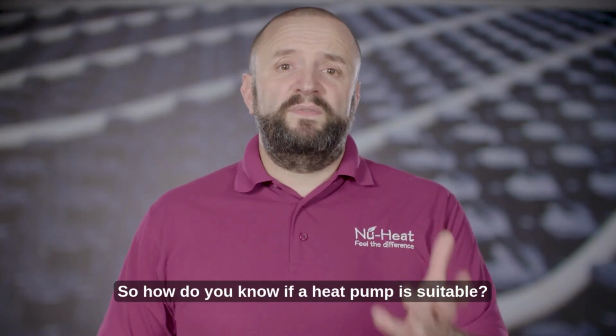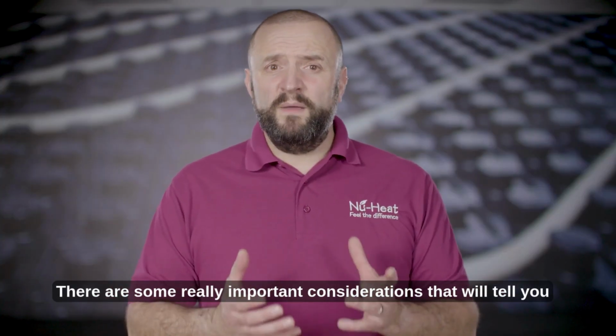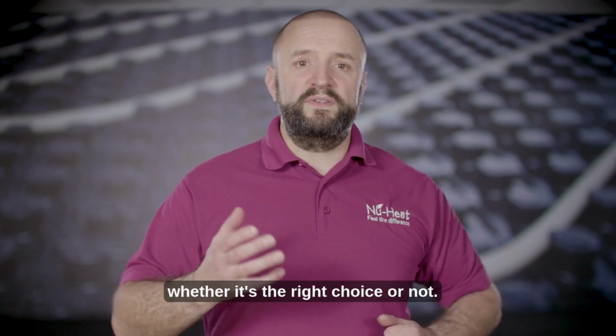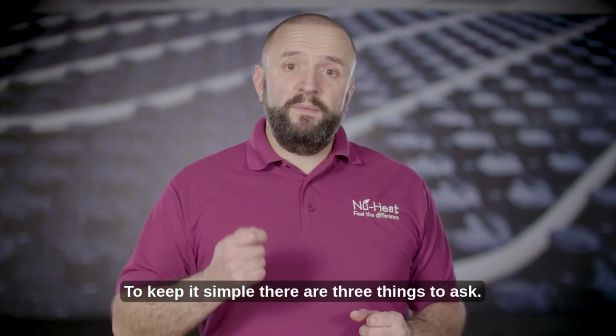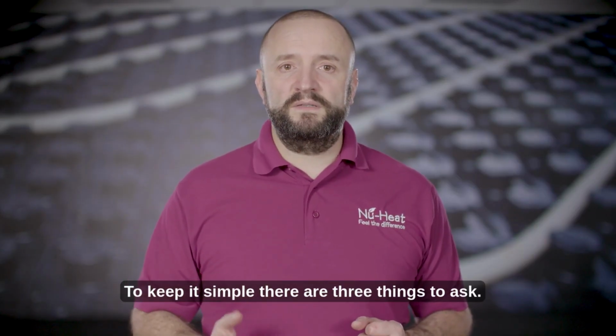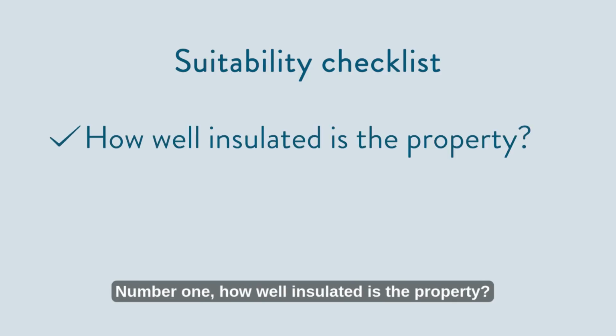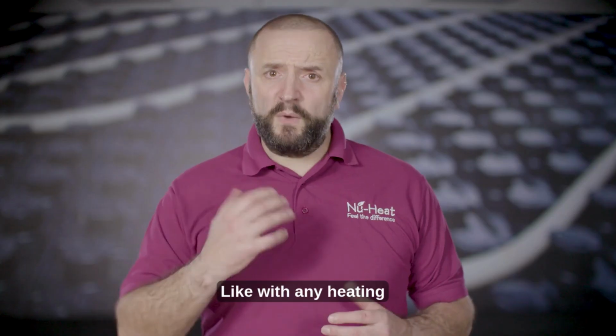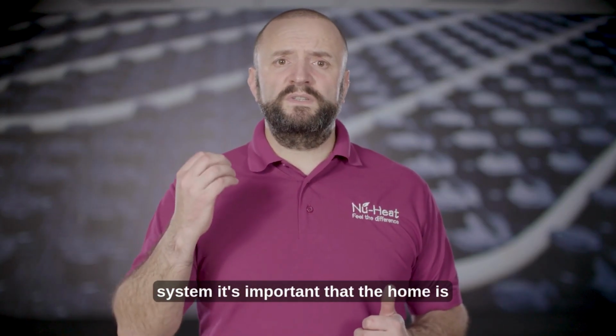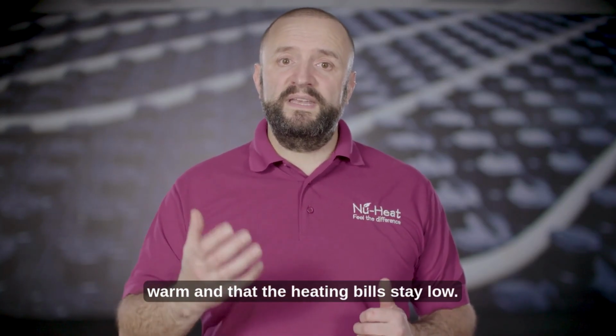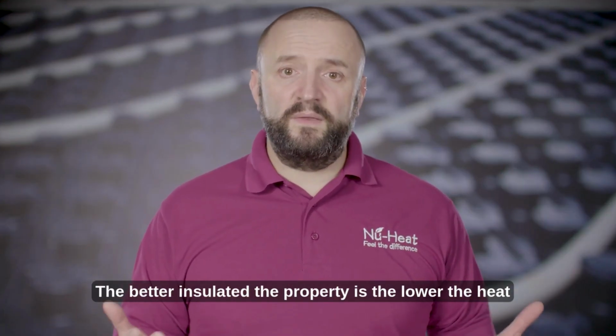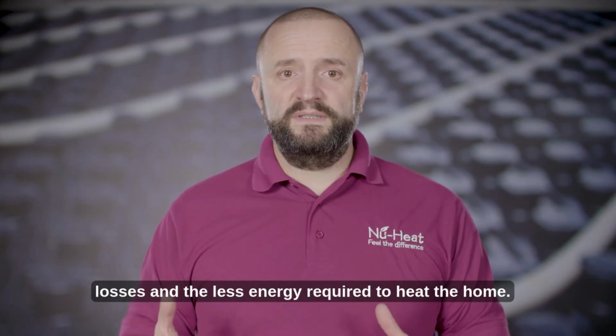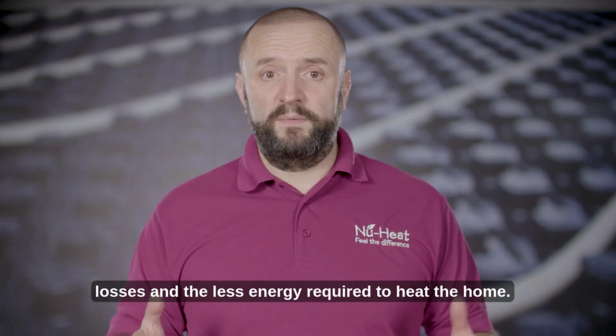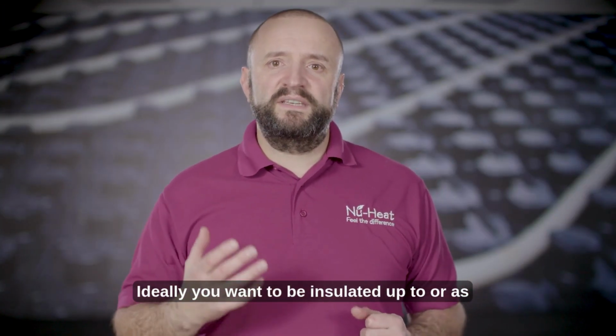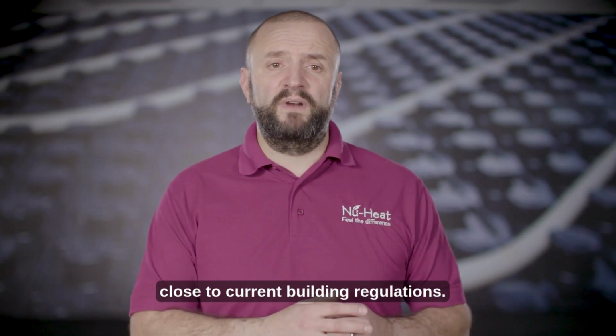So how do you know if a heat pump is suitable? There are some really important considerations that will tell you whether it's the right choice or not. To keep it simple, there are 3 things to ask. Number 1, how well insulated is the property? Like with any heating system, it's important that the home is warm and that the heating bills stay low. The better insulated the property is, the lower the heat losses and the less energy required to heat the home. Ideally, you want to be insulated up to or as close to current building regulations.